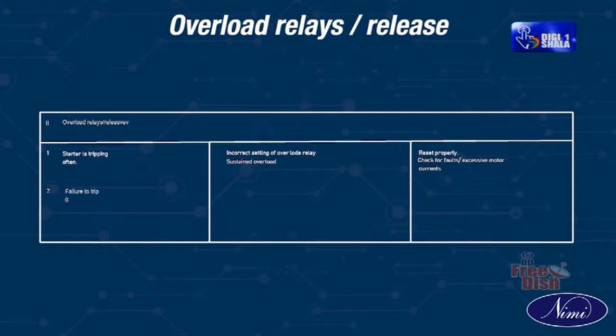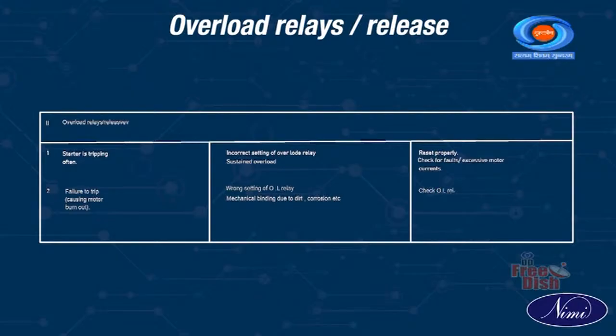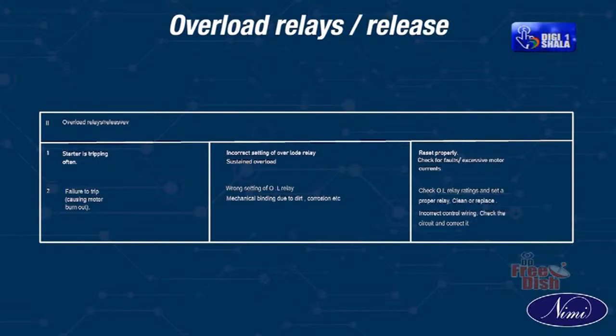2. Failure to trip, causing motor burnout. Wrong setting of overload relay, mechanical binding due to dirt, corrosion, etc. Check overload relay ratings and set a proper relay. Clean or replace. Incorrect control wiring. Check the circuit and correct it.